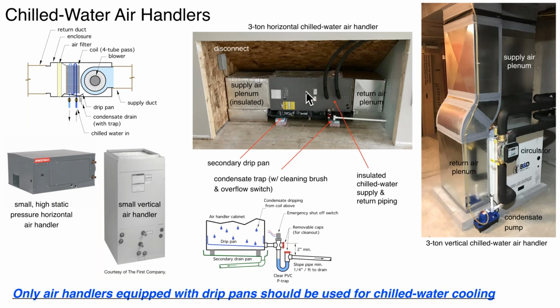Here is a horizontal air handler installed. It's actually sitting on a secondary drain pan. The secondary drain pan is there to catch anything that might leak through the bottom of that unit. Over time, that primary drain pan could corrode and simply fail, and you start to get a leak. If that air handler is installed over finished ceilings, as is the case here, we don't want that condensate dripping down on that ceiling. So it's just a plastic pan that also has a drain connection to it.